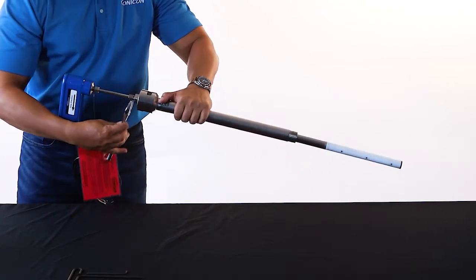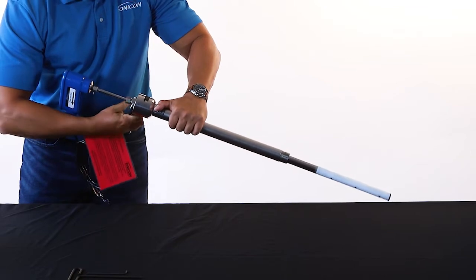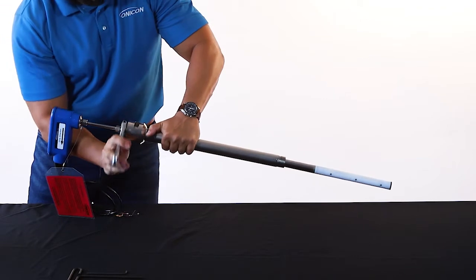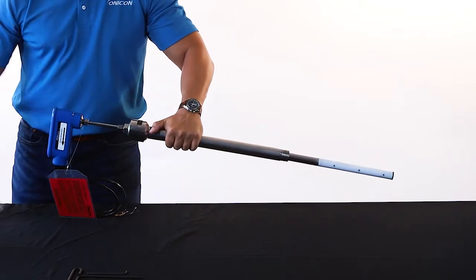Back the preload fitting out of the preload housing by turning the fitting counterclockwise one and a quarter turns. This will set the appropriate preload compression when the meter is installed in the piping system.